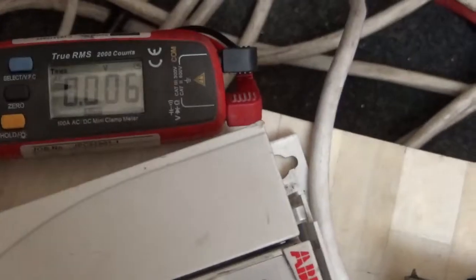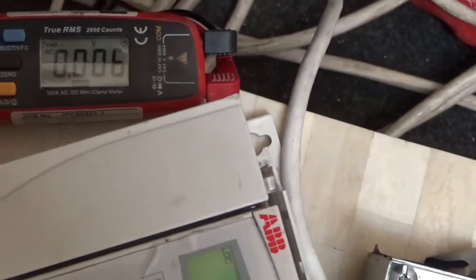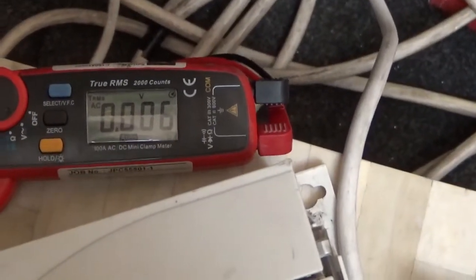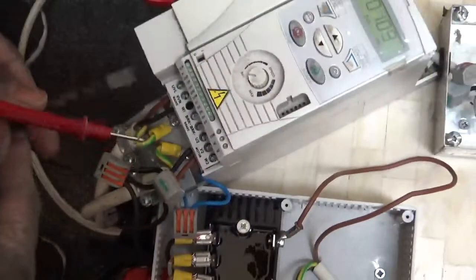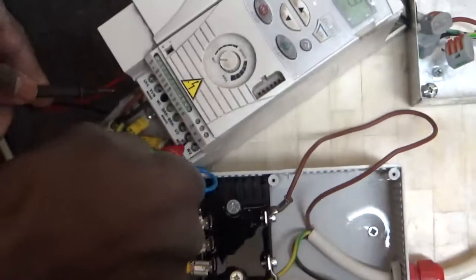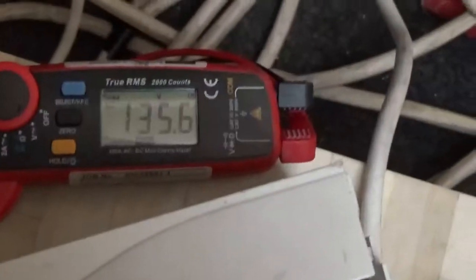Now look, this is where it gets interesting Carlos. If we can now do phase to earth, have you got it on the earth? And look, the voltage there is 135, you see that?